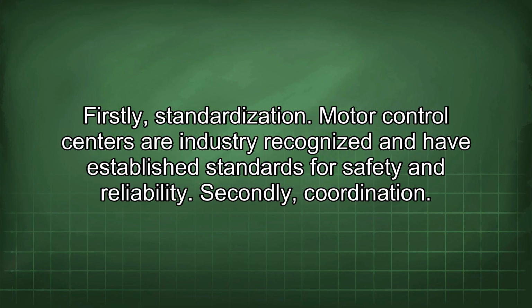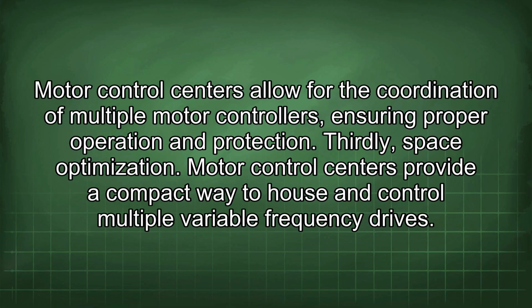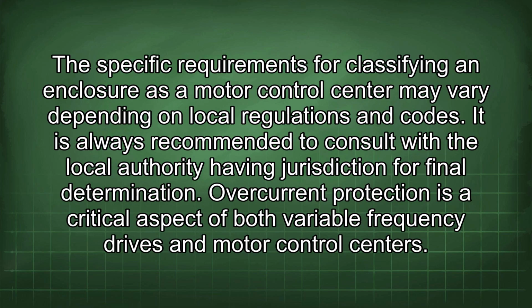Firstly, standardization. Motor control centers are industry recognized and have established standards for safety and reliability. Secondly, coordination. Motor control centers allow for the coordination of multiple motor controllers, ensuring proper operation and protection. Thirdly, space optimization. Motor control centers provide a compact way to house and control multiple variable frequency drives. The specific requirements for classifying an enclosure as a motor control center may vary depending on local regulations and codes. It is always recommended to consult with the local authority having jurisdiction for final determination.